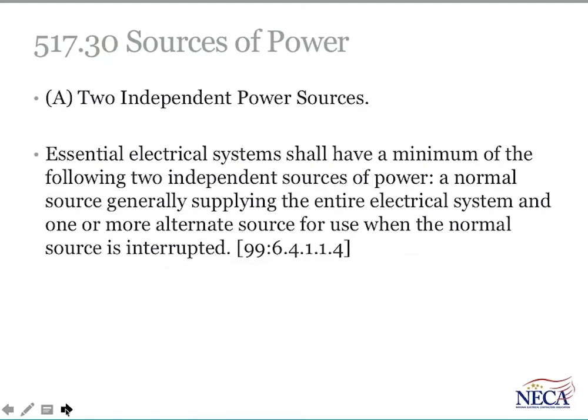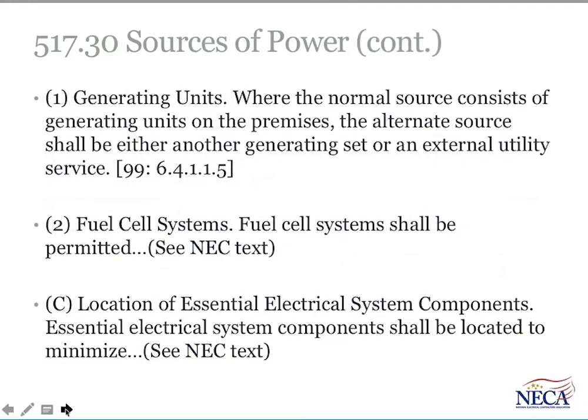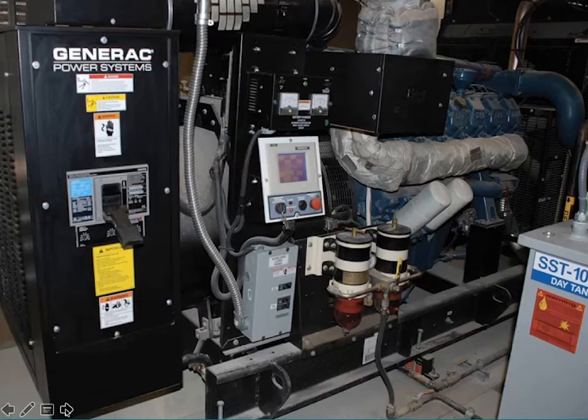So here's some of the language, how it should appear. You see sources of power, generating units is not new, but what is new is fuel cell systems. In Subdivision C, the language ended up reading something like, essential electrical systems components shall be located so as to minimize the effects of anything that might interrupt that power source, instead of consideration shall be given to the location of those components. We're talking about sources like generators and batteries and so forth that are essential to keep the facility running.